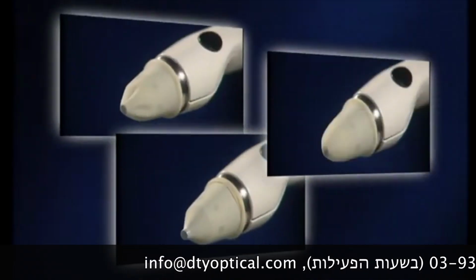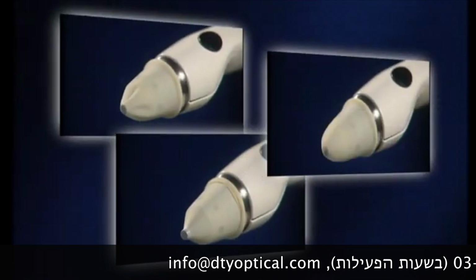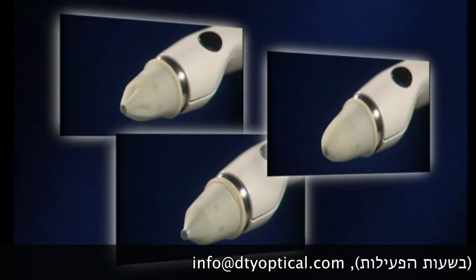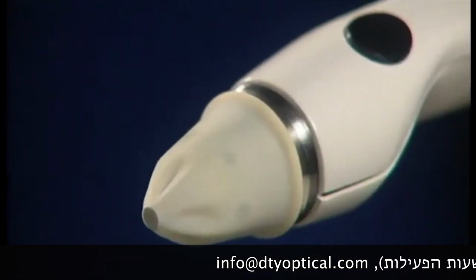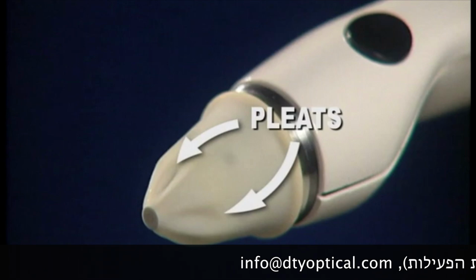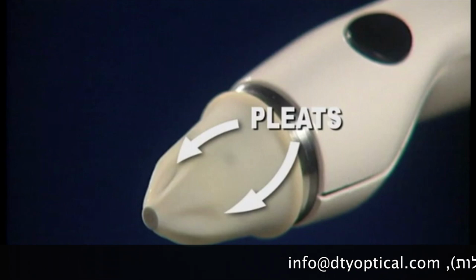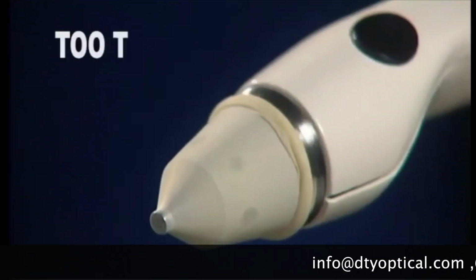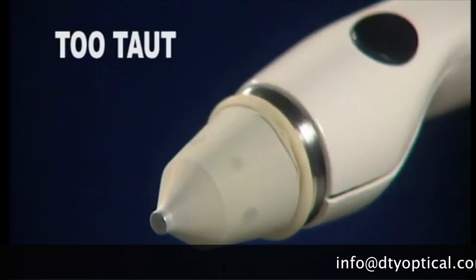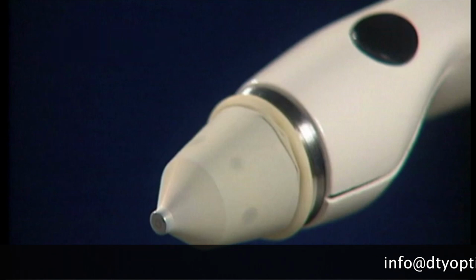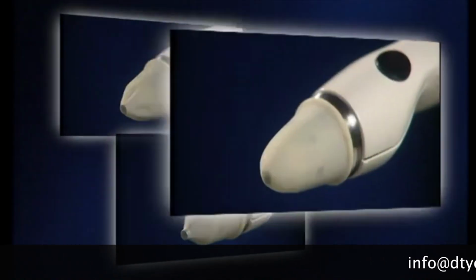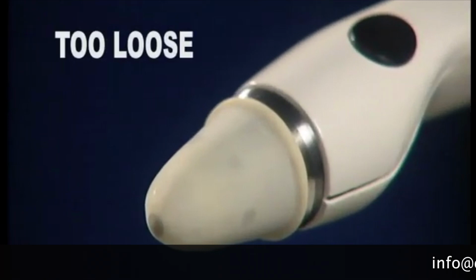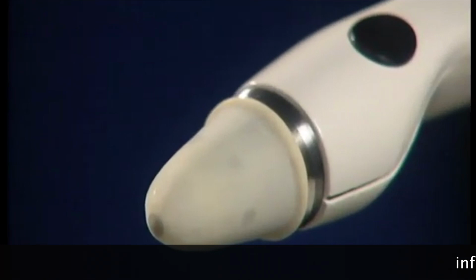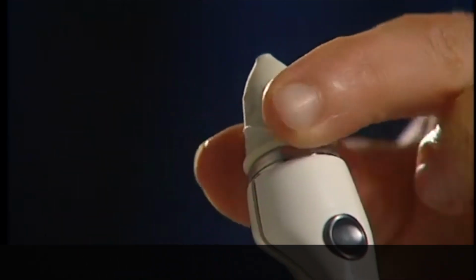However, care must be taken to ensure that the tip cover is not applied too tightly or too loosely over the transducer. This illustrates a tip cover with the proper tension. Pleats like these should be seen, indicating the correct tension and allowing the transducer post to move freely. If too taut, the tip cover might introduce resistance in the micro-movement of the transducer post, which could cause readings which are too high. On the other hand, tip covers should not be too loose so that they form a fold or a crease over the transducer. Adjust the tension until pleats are evident.